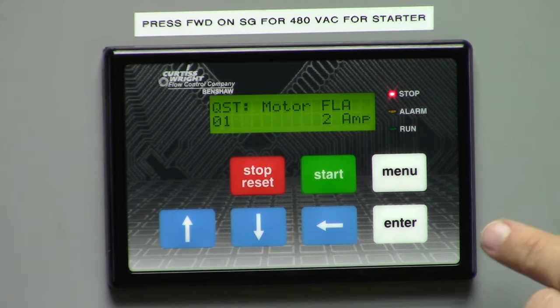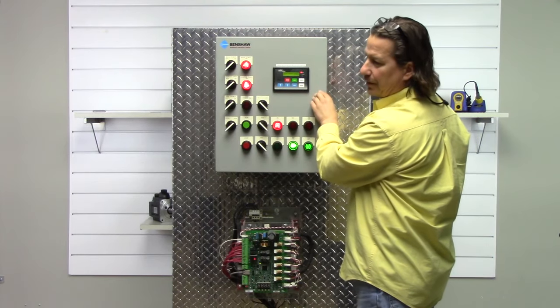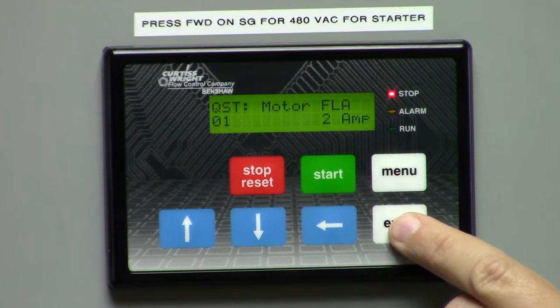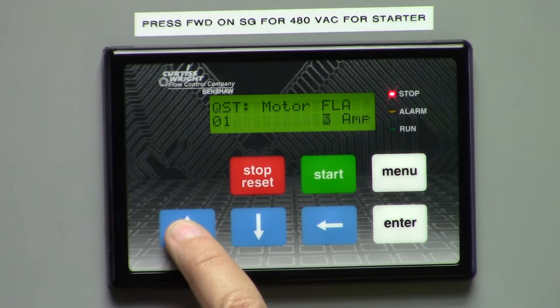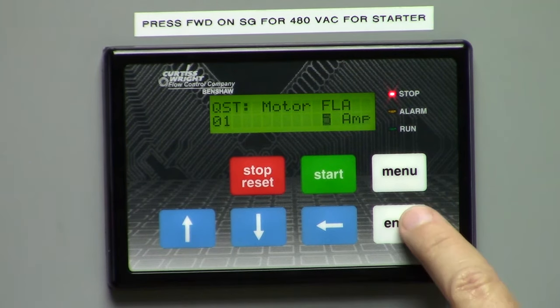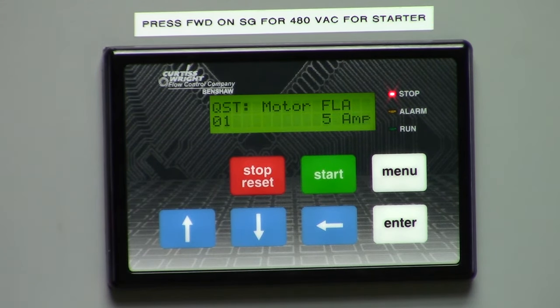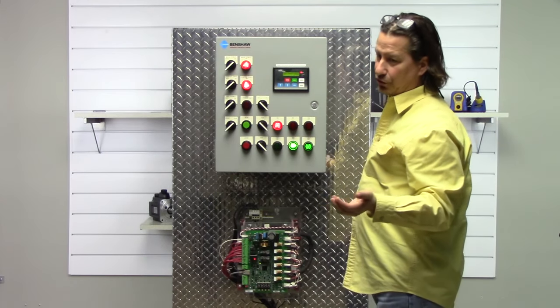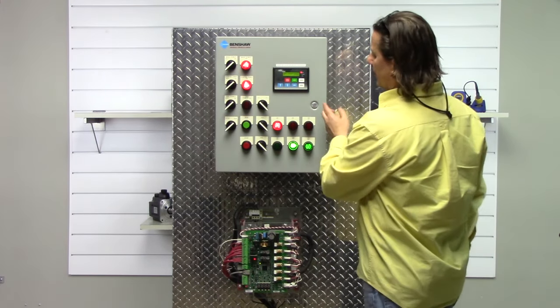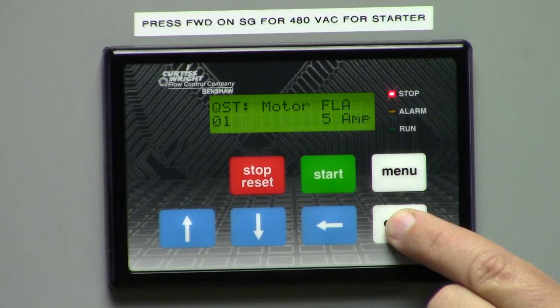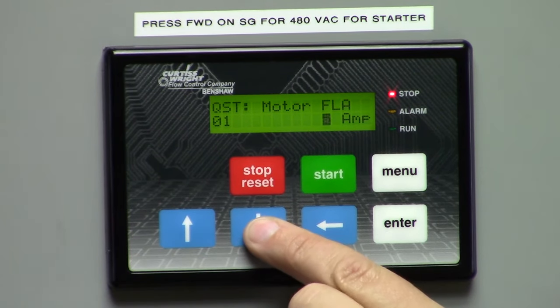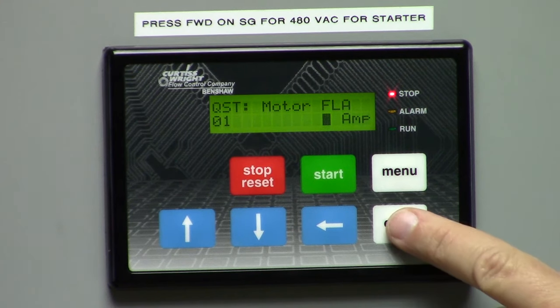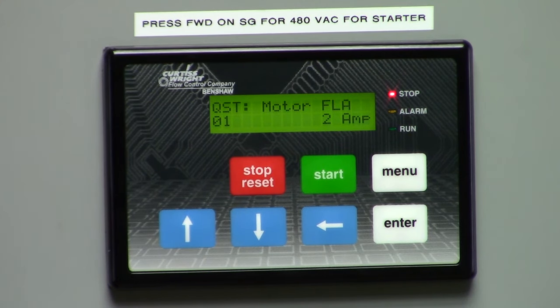Let's say the actual motor current is 5 amps. To change that, you simply push the enter button, put the up arrow to 5, and hit the enter button and it's locked in. I'm going to change it back to 2 because that's what our test motor is. You hit enter, push the down arrow to 2 because that's what our nameplate is, enter, and it locks it in.